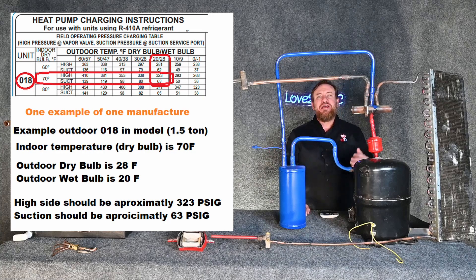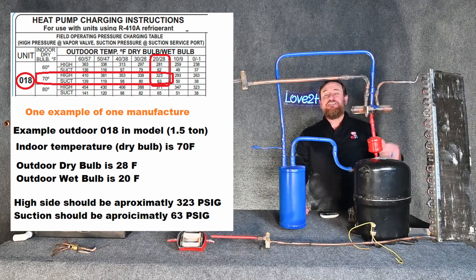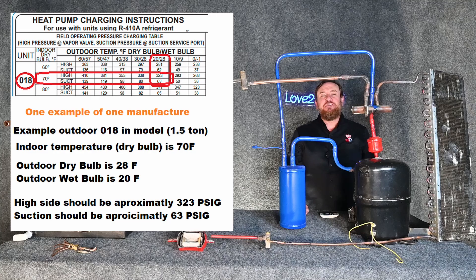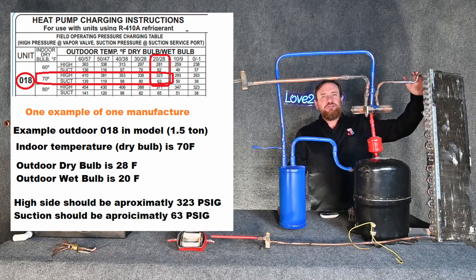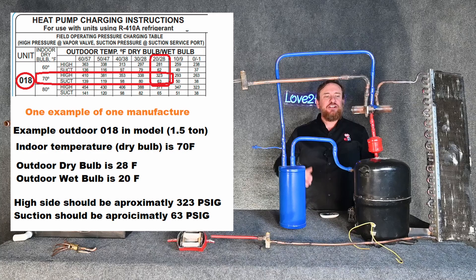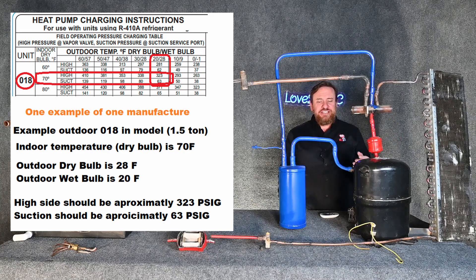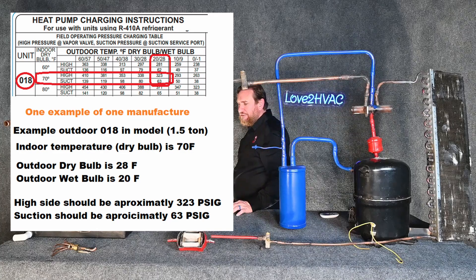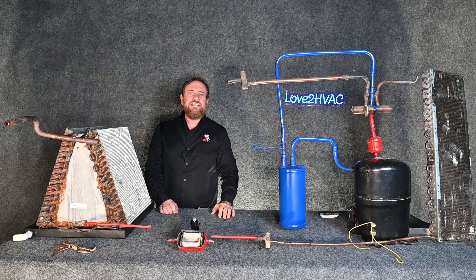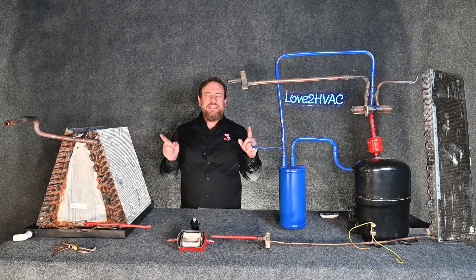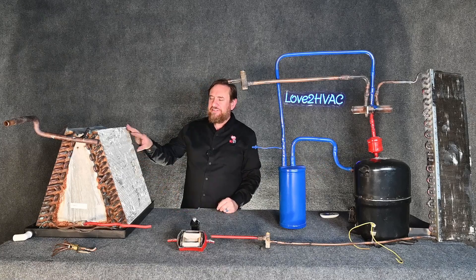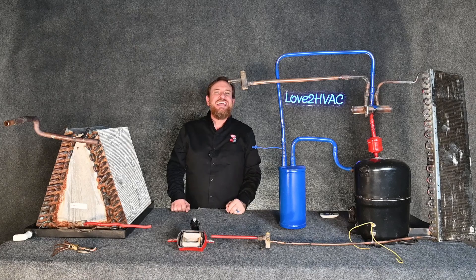That sounds like a great solution, but conditions change and we end up with a very high amount of superheat — all the refrigerant boiling from liquid to vapor very quickly. Maybe it gets cooler inside and warmer outside, which is a very likely possibility. Then we end up having too much superheat at the outdoor coil because the fixed orifice can't control it, superheat gets too high to the compressor, compression ratio gets too high, superheat coming in is too high, superheat coming out is even higher, and we end up cooking the compressor. So fixed orifice metering devices are popular with technicians because the metering device itself is unlikely to fail, but it has consequences on the rest of the system — mainly the compressor — and also affects performance of the evaporator coil in summer and the outdoor coil in winter.